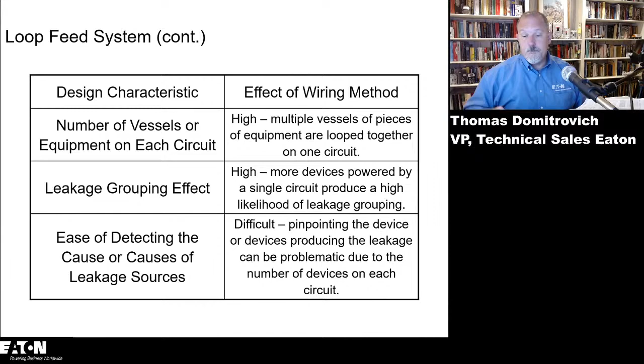Another approach, which is what we saw in that marina in Hilton Head, is individual feeders going to each of these pedestals. That helps, because if that pedestal has an issue, that device trips. So if I feed these on individual feeders, I call it a feeder circuit because there's usually a little power distribution panel in here with multiple receptacles, etc. Technically, I could argue that's a feeder and not a branch circuit to an appliance, but we can have that debate all day.